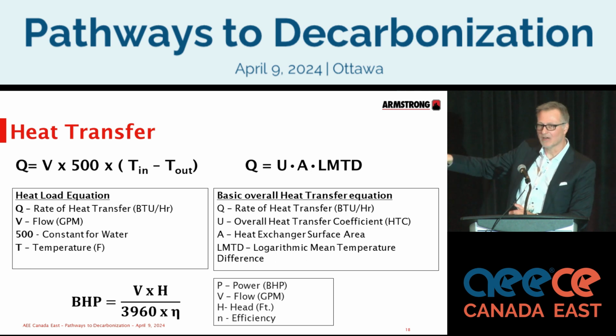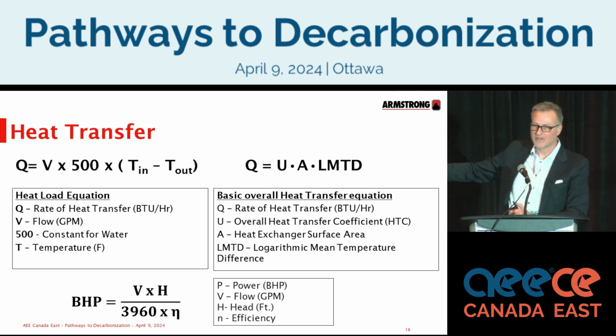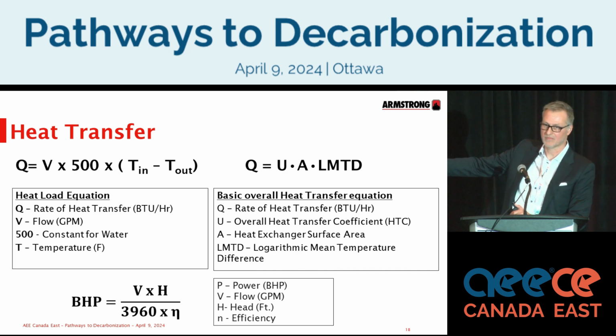And what's key in all of this is that in our typical control strategies, we're operating off of set points and speed. But if you look at the math, if you're able to factor in the efficiency of your equipment, the higher the efficiency at its operating point, the less power you're going to consume. And that's why I show the math here, because it's all straightforward. If you understand the math, this is where you're going when you start looking at optimization.